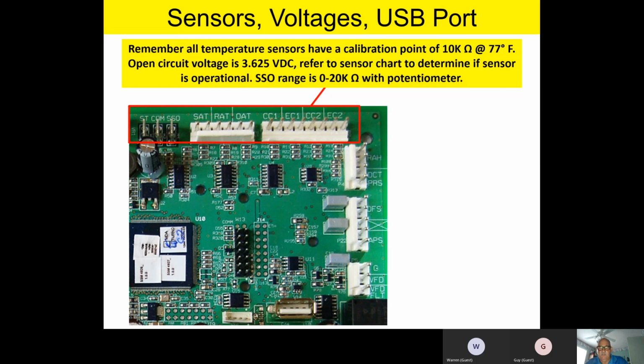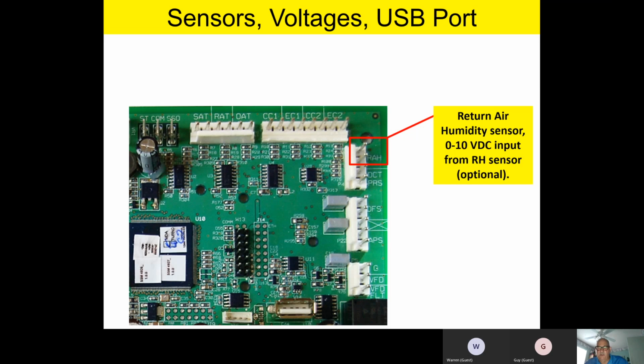All right, as we come down the right-hand side of the board, we have a return air humidity sensor that's going to be used for enthalpy calculations and economizer calculations. That return air humidity sensor is a 0 to 10 volt input from a relative humidity sensor, and that's an optional input, so it doesn't come from the factory that way unless you've got some factory-installed options that require that return air humidity sensor.